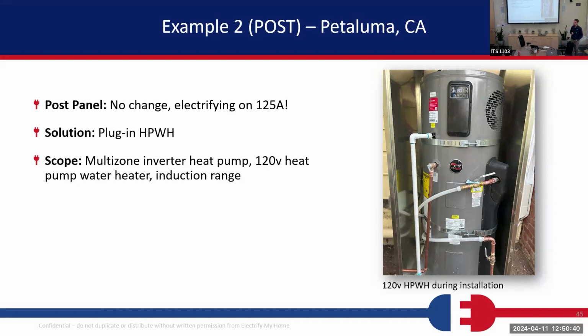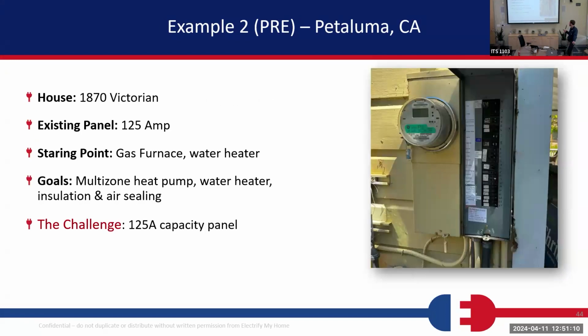In this case, no, there was sufficient breaker space that we would just pull the breakers out of it, and the old breakers that were installed are now like a fire risk. I've done EV projects before, we go to those EV bonds, they have like Cisco breakers or something, 40 years ago. You cannot use these, they will kill people, but no one changes them out because you're not required to until you do a retrofit or an electric upgrade. Yeah, exactly. So in this case, it was still a modern panel, at least, even though the house was ancient. So we were okay in terms of safety.